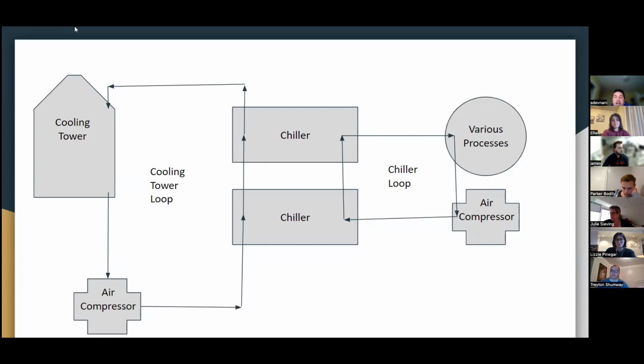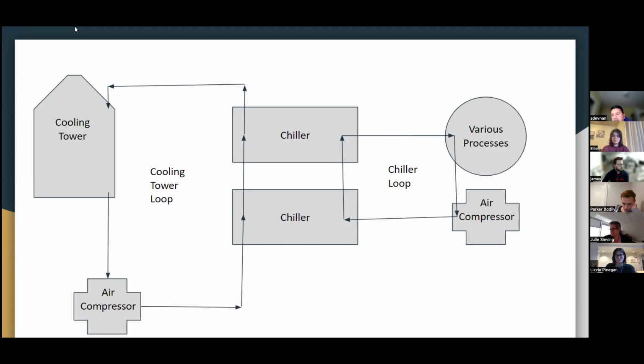The reason I brought that up is remember, you're going to have to cut a closed loop. Your chiller loop is a closed loop. So when you cut that open to remove the compressor, you've also got to seal that back up. And when you cut this part up, you're going to lose some amount of water. I don't know how much. If it ends up being a large volume, then you have to get the chemistry of that water back into play. Otherwise, you can start having many things grow inside that water if it's not spinning.